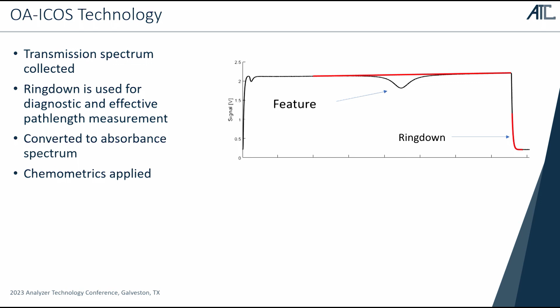But we scan the spectrum and you get a peak, right? This is fundamentals. This isn't a real sample. And you build a calibration over a spectral region that incorporates that absorption and any interferences that would impact that. And when the laser gets pulsed off, you can measure the ring down time as a diagnostic tool. So we're collecting this entire spectrum, albeit over a very narrow region, and using the ring down time as a diagnostic. Obviously, we convert this from transmittance to absorbance, so the peaks go up, which is a little bit more preferred.